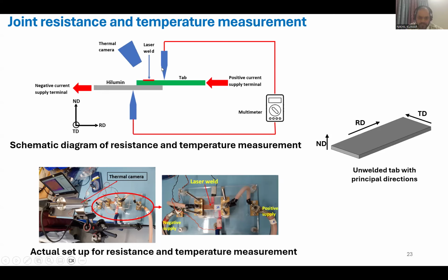We made some arrangement with probes. One probe connects close to the weld on the tab, and the other probe connects to the bottom face of the bottom sheet. Those probes are very close to the weld so we can capture the voltage drop across the weld only.